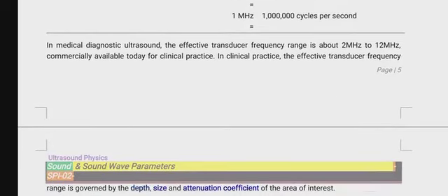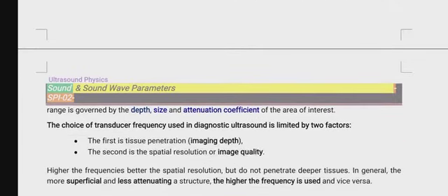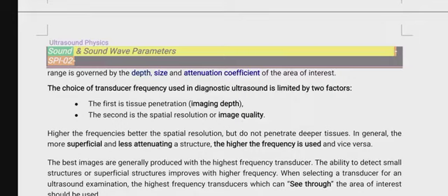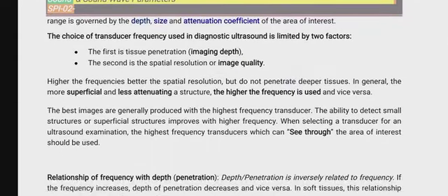In medical diagnostic ultrasound, the effective transducer frequency range is 2 MHz to 12 MHz, commercially available today for clinical practice. In clinical practice, the effective transducer frequency range is governed by depth, size, and attenuation coefficient of the area of interest. The choice of transducer frequency used in diagnostic ultrasound is limited by two factors. It's very important you know this, because we're now beginning to dive into what image optimization would mean in practice.